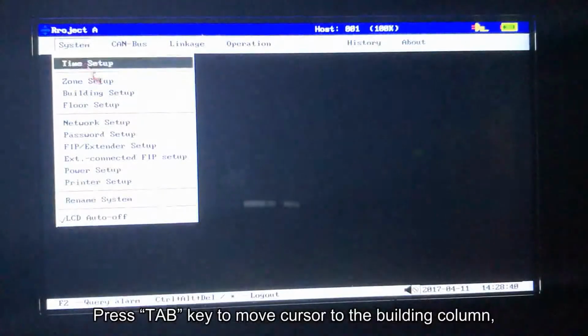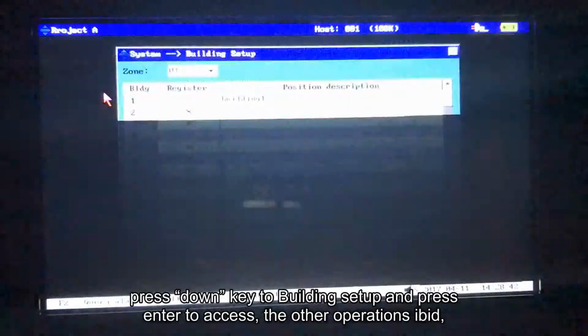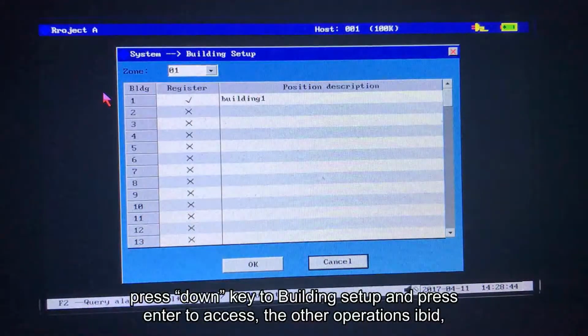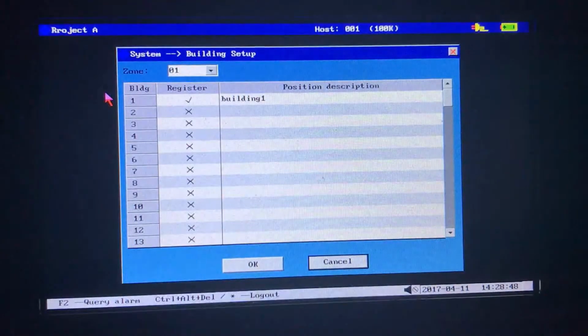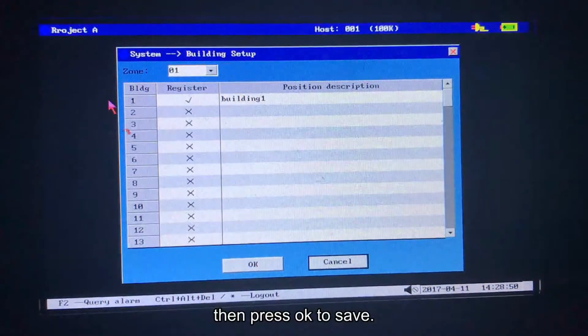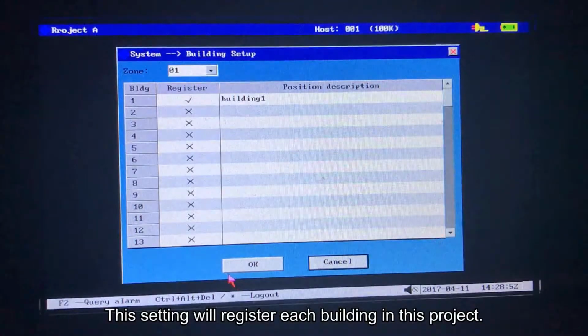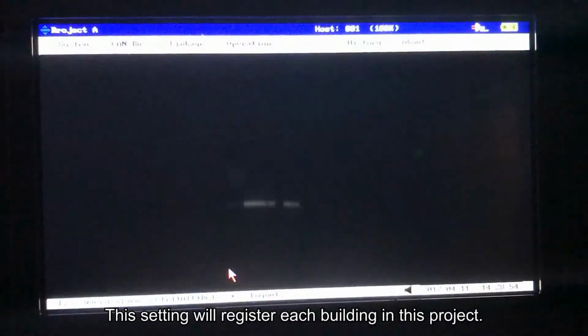Press tab key to move cursor to the building column. Press down key to building setup and press enter to access. The other operations are the same. Then press OK to save. This setting will register each building in this project. The above setting could be set in accordance with actual buildings.